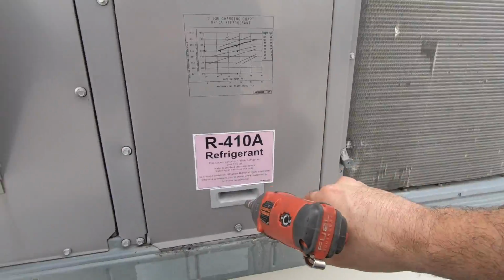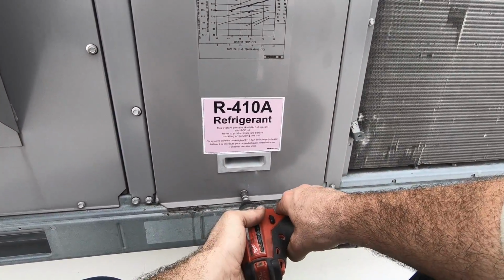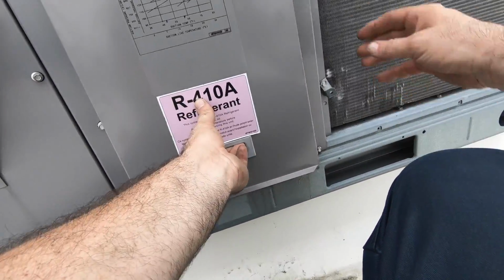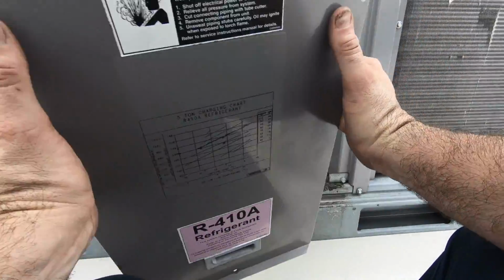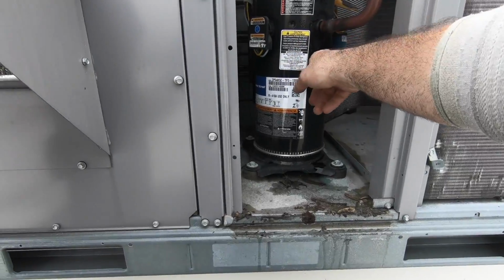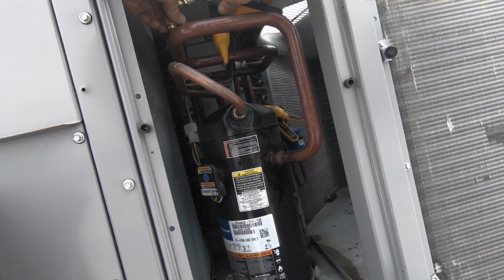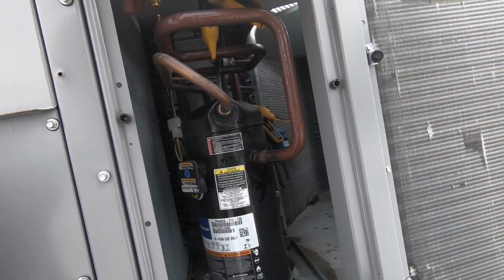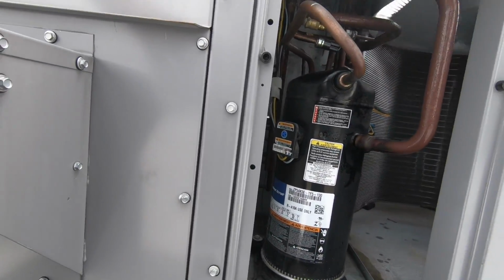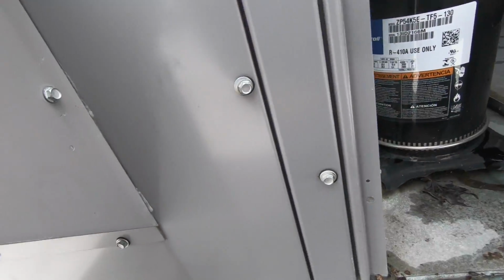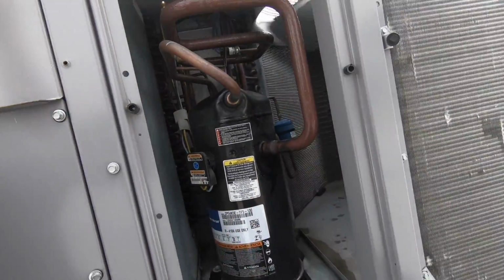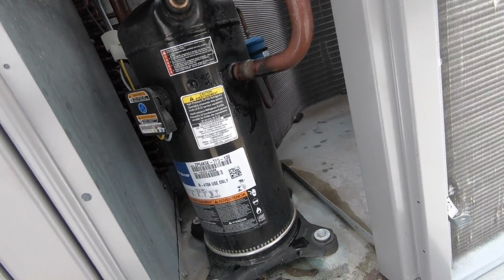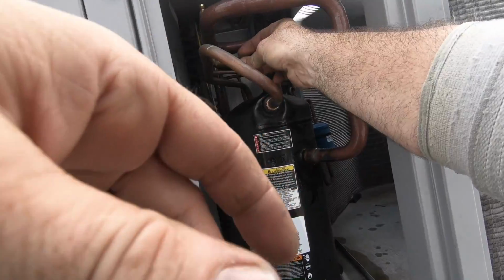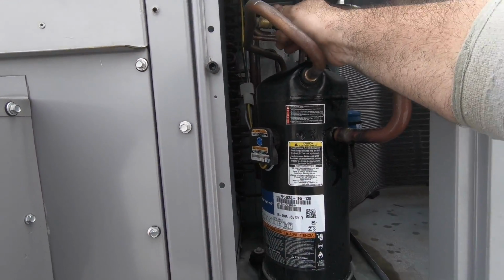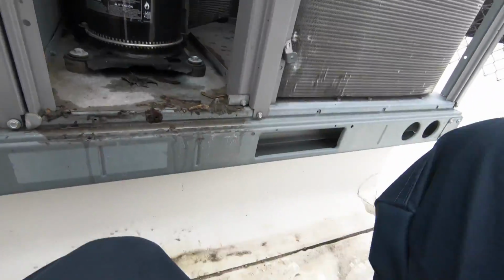My compressor is not supposed to be saturated. Let's just see. Maybe a little bit by the suction pipe, but you don't want a saturated compressor. Got a little bit, but that's telling me I could disconnect my tools and close this up. Be careful when you're ever in here because that's hot and you got a blade spinning really fast right up top. Let's close that up. Now I'm happy with how this job turned out.